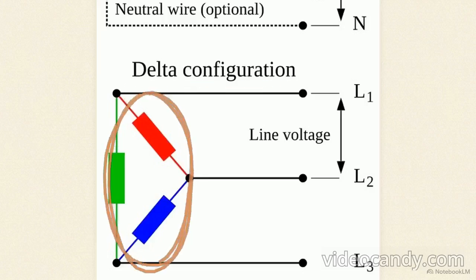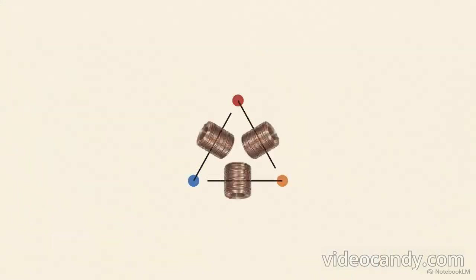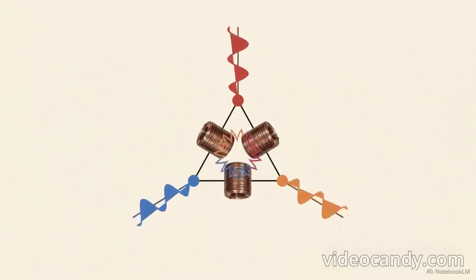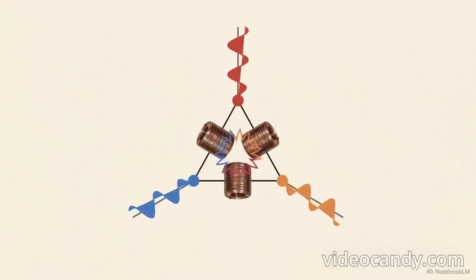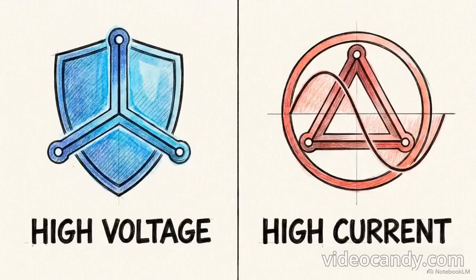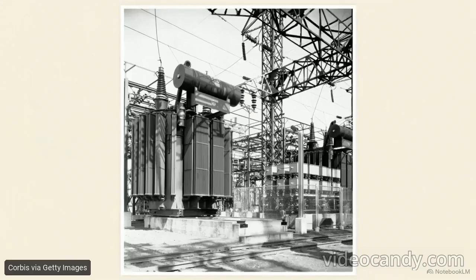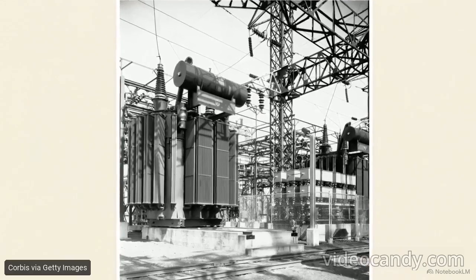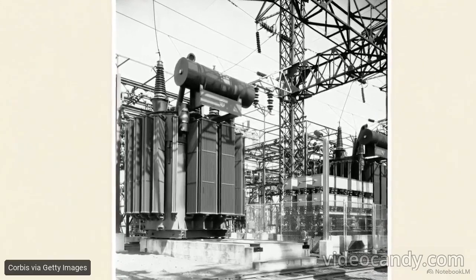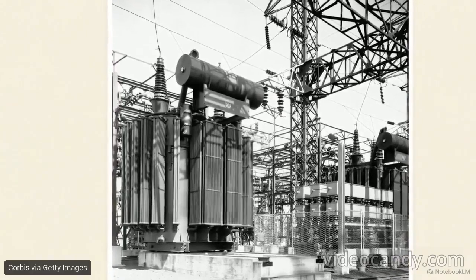Now look at the lower schematic. This is the delta connection. It forms a closed loop, completely eliminating that central neutral wire. Delta excels at harmonic trapping. The closed delta mesh provides a continuous circulation path for third harmonic currents, keeping them out of the transmission lines and ensuring a clean sinusoidal output. Engineers deploy Y to save money on insulation in high-voltage scenarios, and they deploy delta to maintain harmonic stability in high-current applications.